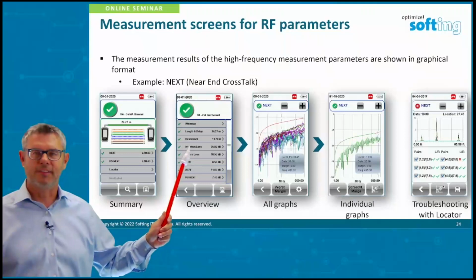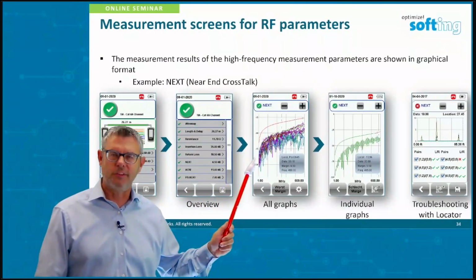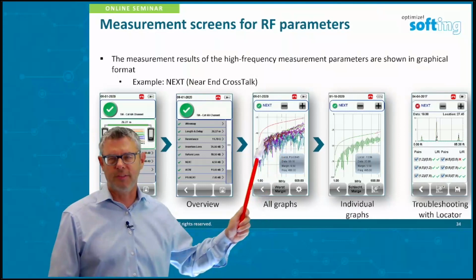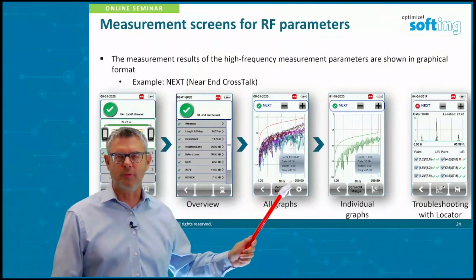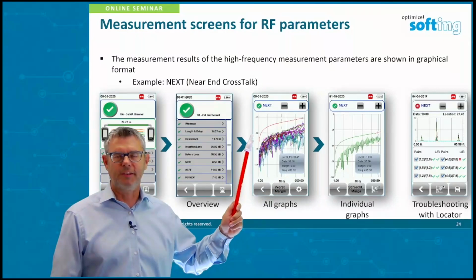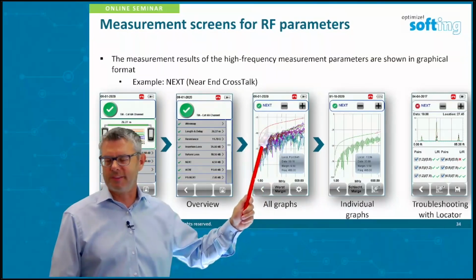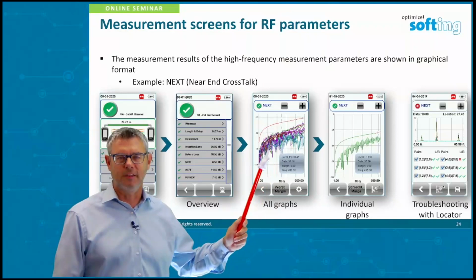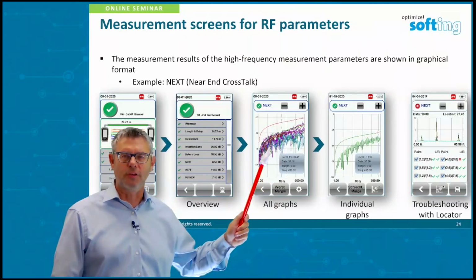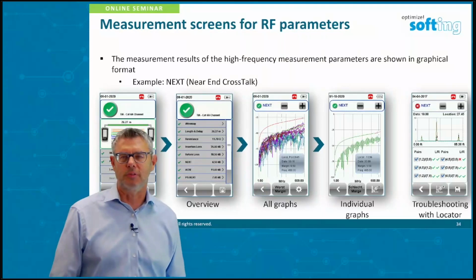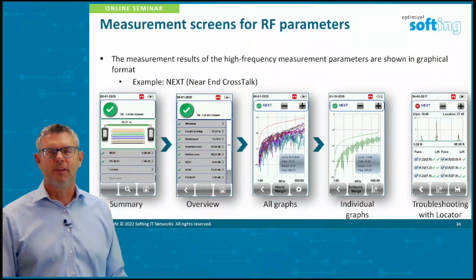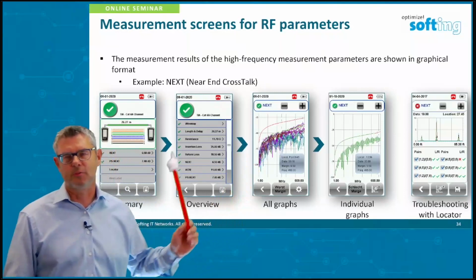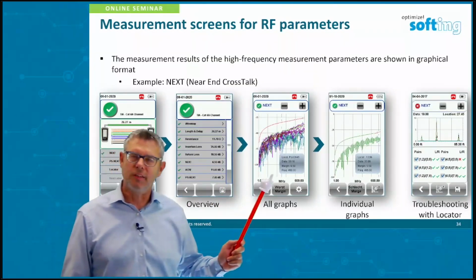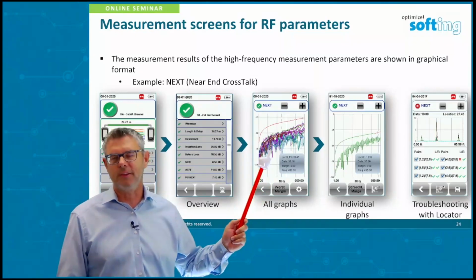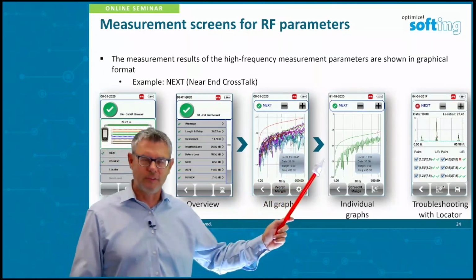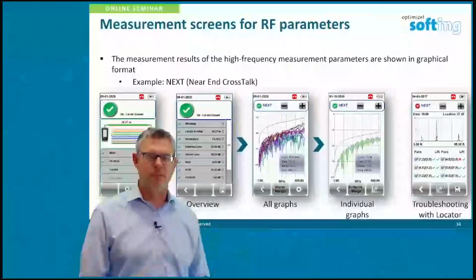If we open up the next level of screen, we get a graphical interpretation of the next measurement. It's a measurement over frequency. This line is the limit line given by the selected standard, and these are the measurement curves we get out of these measurements, for the 12 measurements we have to do next. There's a cursor which indicates the worst margin. We can even dig deeper and isolate individual pairs and have a look at them. So we get a lot of information from the test.